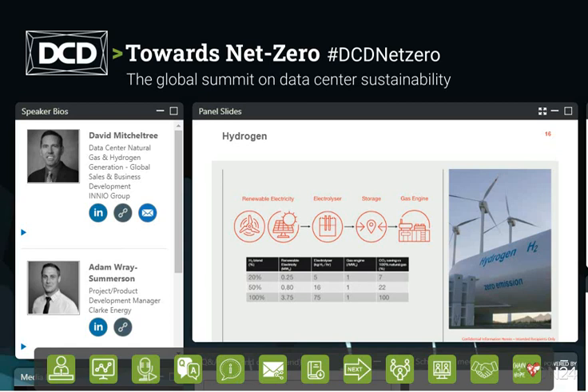If we think about renewable electricity being used as the medium to produce the energy carrier, i.e. hydrogen, then the table here illustrates the amount of hydrogen required to provide a certain percentage by volume of fuel to a gas engine, and how much power is needed from renewables to produce each kilogram required for that given fuel. So for us to get 1 megawatt of electrical power using a 20% hydrogen blend into natural gas, we need to put 250 kilowatts worth of renewable power to produce 5 kilograms an hour of hydrogen. That gives us a 20% blended fuel, resulting in a 7% reduction in CO2 emissions.